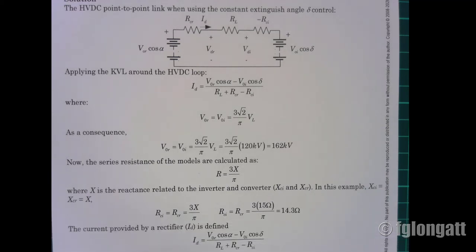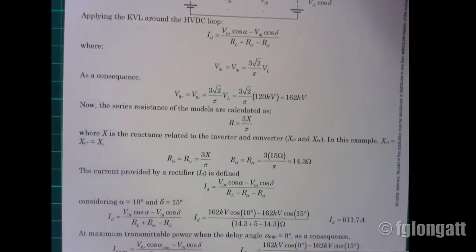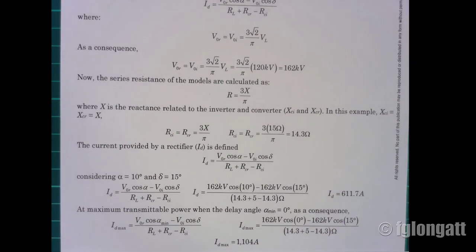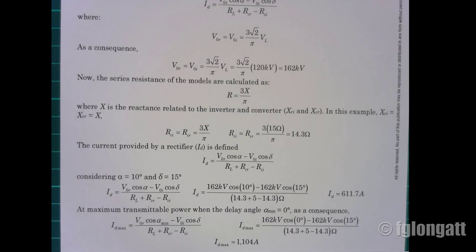Now using the basic equation derived from Kirchhoff's Voltage Law to obtain the current from the rectifier: for the first question, with alpha equal to 10 degrees and delta equal to 15 degrees — that is the maximum angle from the inverter, starting from delta_0 of 10 degrees with the 5-degree margin — the current for this specific operating condition is 611 amps.